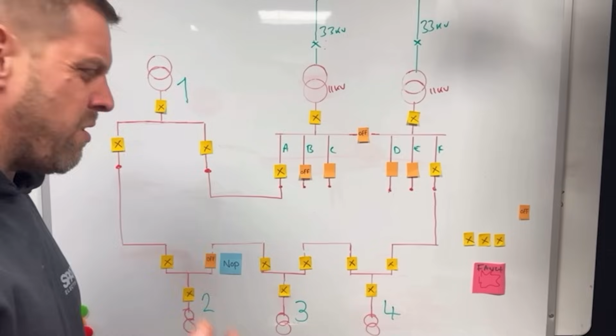What we're going to do is, I'm not going to do a fault because that would mean you'd lose the supply. We want to do a cable test on the piece of cable that goes between substation 3 and 4. So we want to work on this section of cable just here.